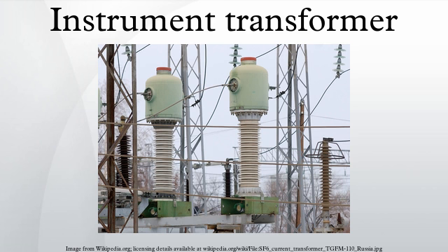Current transformers are often constructed by passing a single primary turn through a well-insulated toroidal core wrapped with many turns of wire. This affords easy implementation on high-voltage bushings of grid transformers and other devices by installing the secondary turn core inside high-voltage bushing insulators and using the pass-through conductor as a single-turn primary.